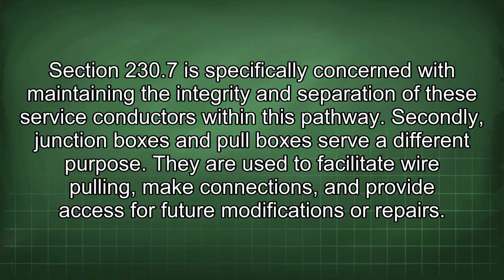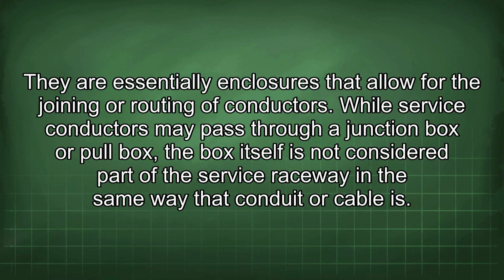Secondly, junction boxes and pull boxes serve a different purpose. They are used to facilitate wire pulling, make connections, and provide access for future modifications or repairs. They are essentially enclosures that allow for the joining or routing of conductors. While service conductors may pass through a junction box or pull box, the box itself is not considered part of the service raceway in the same way that conduit or cable is.